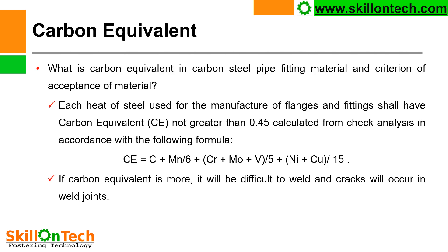Carbon Equivalent — what is the carbon equivalent in carbon steel pipe fitting material, and what are the criteria of acceptance? Each heat of steel used for the manufacture of flanges and fittings shall have carbon equivalent CE not greater than 0.45, calculated from check analysis in accordance with the following formula: CE = C + Mn/6 + (Cr + Mo + V)/5 + (Ni + Cu)/15.